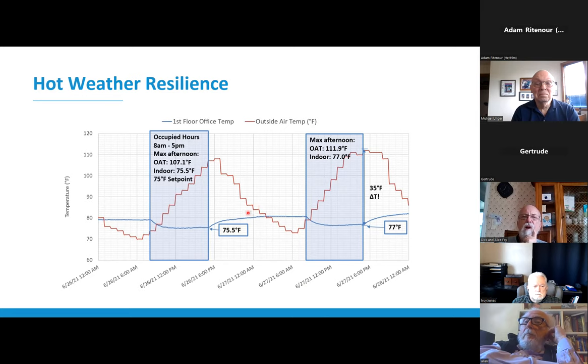So even on these back-to-back days that were well over 100 degrees, the office actually stayed within 2 degrees of the 75 degree set point. So you'll see here on the hottest part of the second day, there's a 35 degree delta between the outside and the indoor air temperatures. And we only floated up to 77 degrees during the occupied hours that we were in the office. So it does work even if we cut our cooling capacity by 41%.